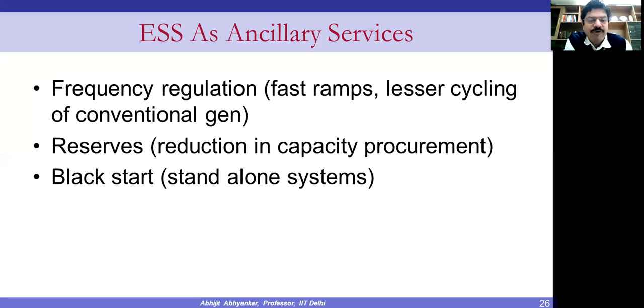You can use them for reserves that will lead to reduction in capacity procurement, which I just explained, and this can be used as black start as well. When the system goes into complete collapse or blackout, it cannot just start like this. There is a standard, very complex and painful process through which you energize the whole system, and that's called black start. Those generators which provide this facility are called black start units. So batteries can provide for the same.